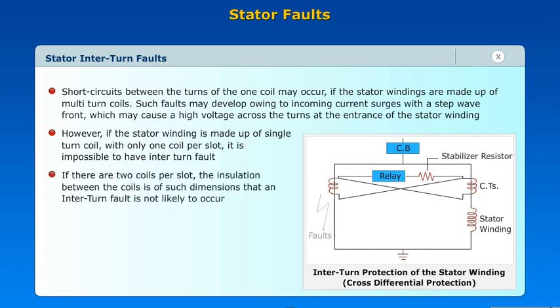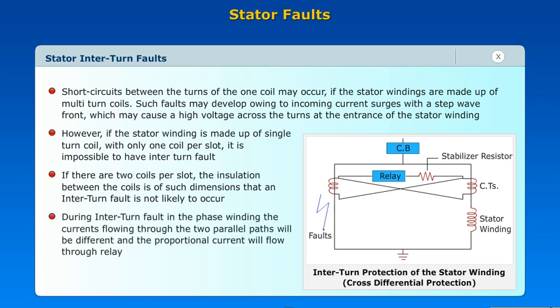If there are two coils per slot, the insulation between the coils is of such dimensions that an inter-turn fault is not likely to occur. During an inter-turn fault in the phase winding, the currents flowing through the two parallel paths will be different and the proportional current will flow through the relay.